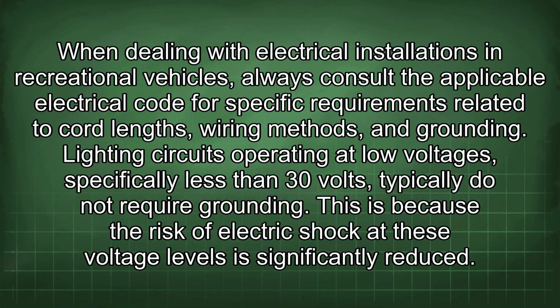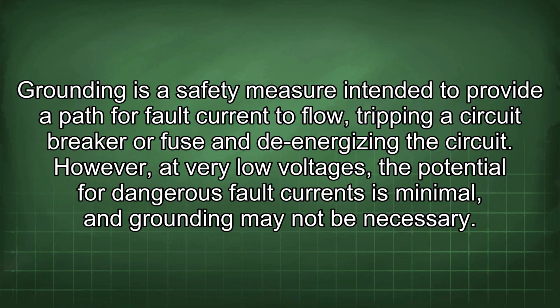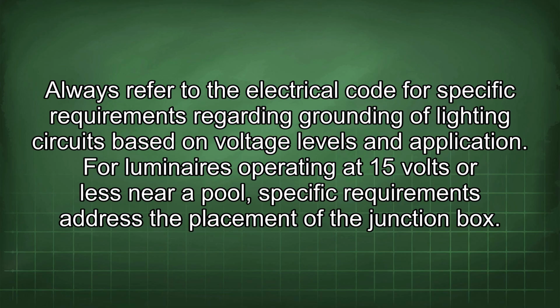Lighting circuits operating at low voltages, specifically less than 30 volts, typically do not require grounding. This is because the risk of electric shock at these voltage levels is significantly reduced. Grounding is a safety measure intended to provide a path for fault current to flow, tripping a circuit breaker or fuse and de-energizing the circuit. However, at very low voltages, the potential for dangerous fault currents is minimal and grounding may not be necessary. Always refer to the electrical code for specific requirements regarding grounding of lighting circuits based on voltage levels and application.